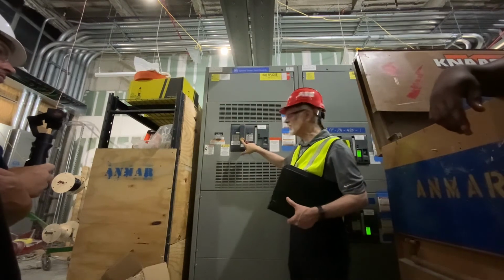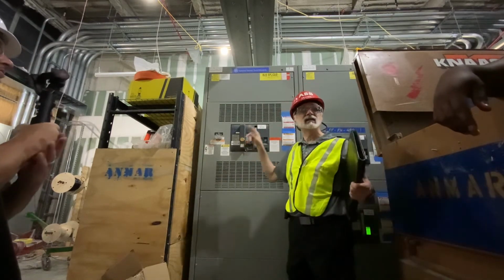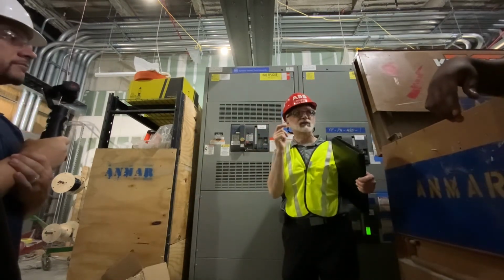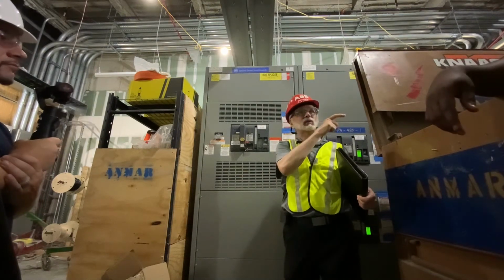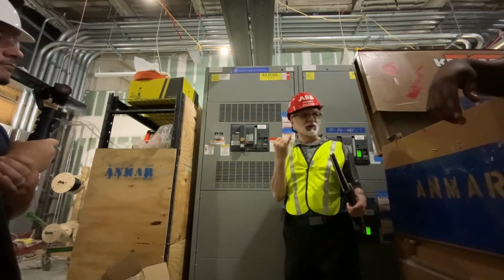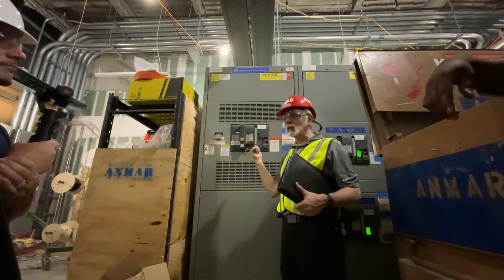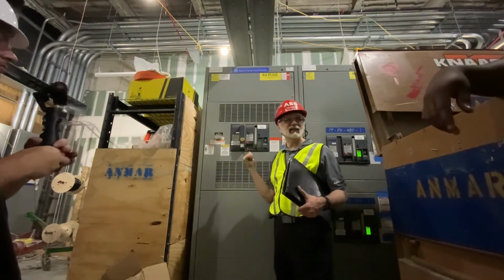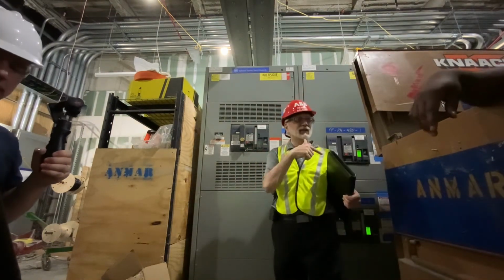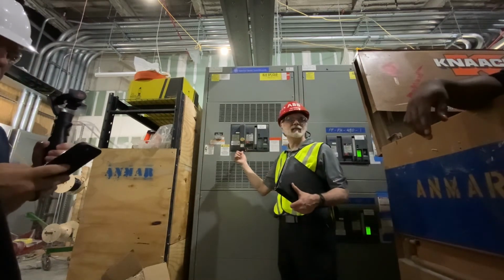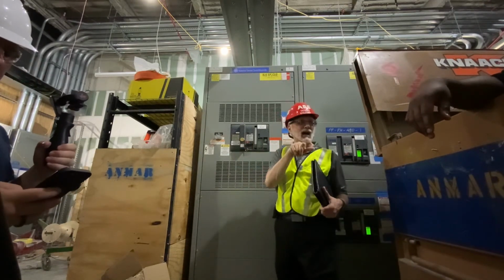As you can see, there is no key in the tie breaker, because this is a 2 out of 3 breaker scheme. So 2 of the breakers will always have a key in them, and 1 of them will not. This is the normal operation. The tie doesn't have the key in it, but if you were going to single end, the tie would have a key in it, and one of the mains would not have a key.